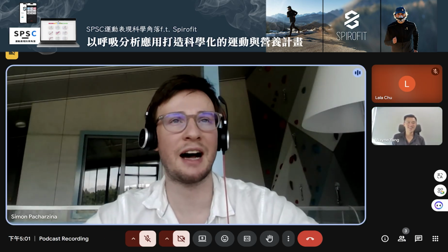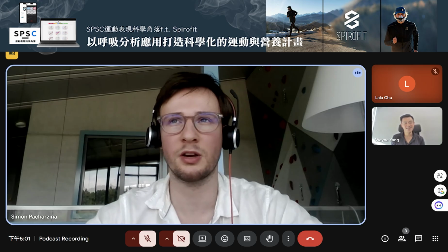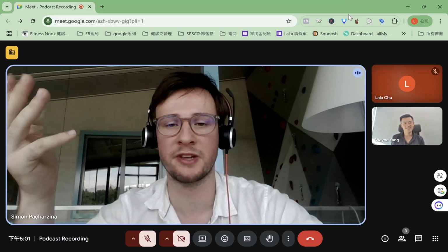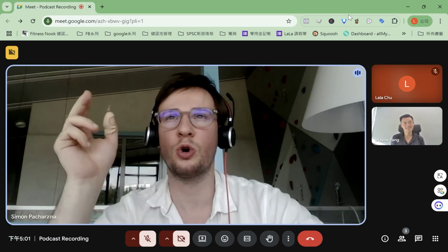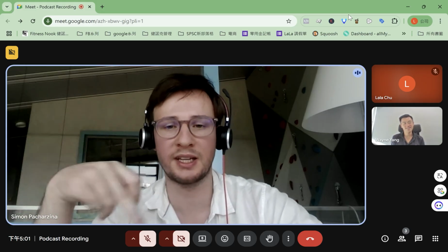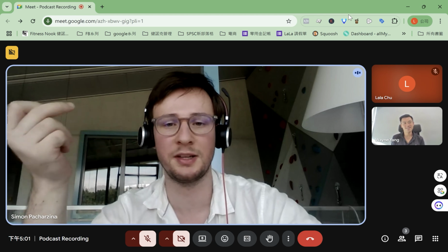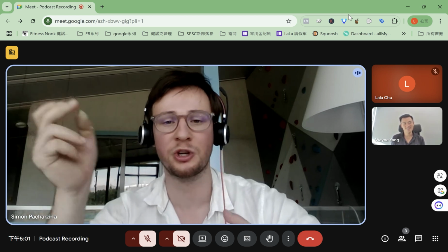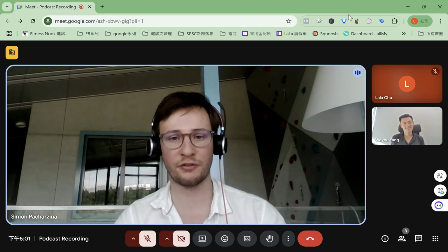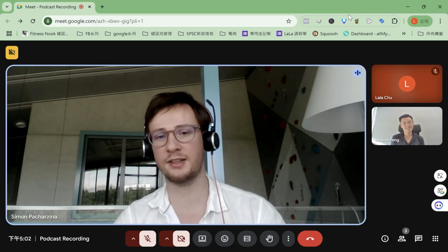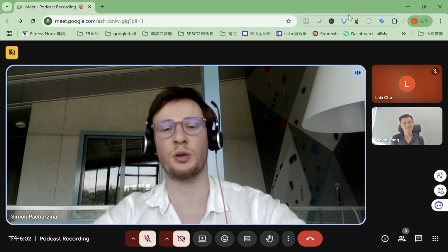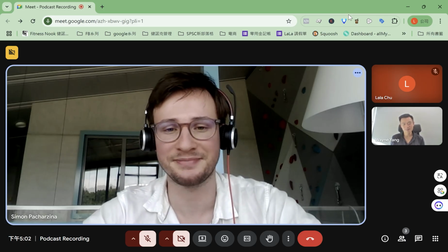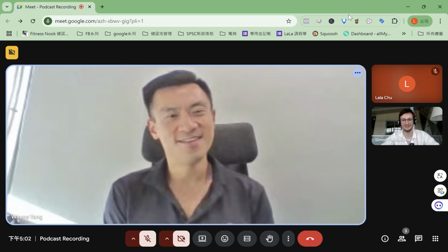Important for the device after using it is that your exhaling humidity is 100%, so the humidity increases a lot. So we have a system where the pump will keep going after you complete your measurement until the humidity reaches a certain threshold where we say it's safe to shut off the device. There won't be any water inside the measuring chamber. That's what we do to keep out excessive humidity. Perfect. Thank you so much for the tip.